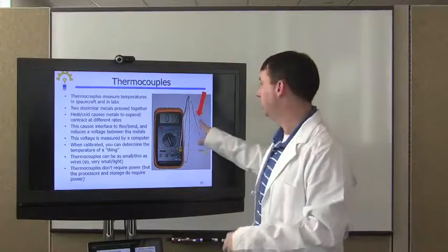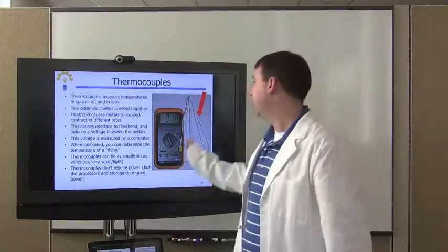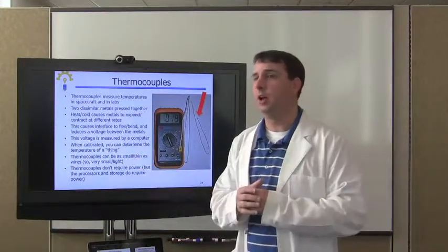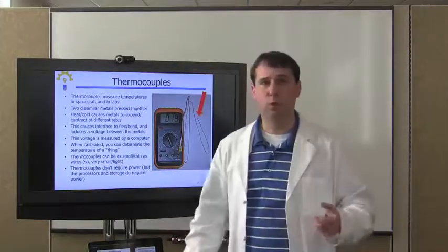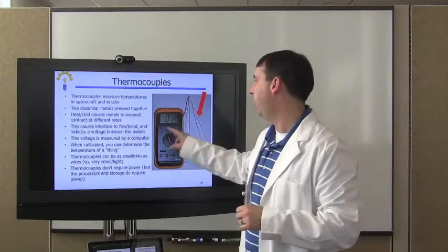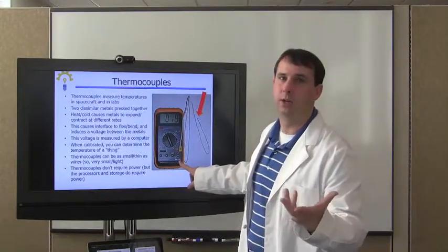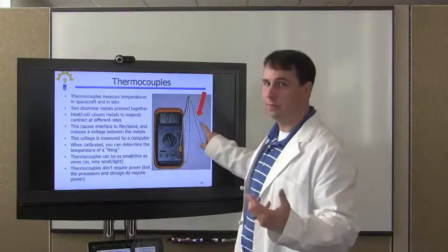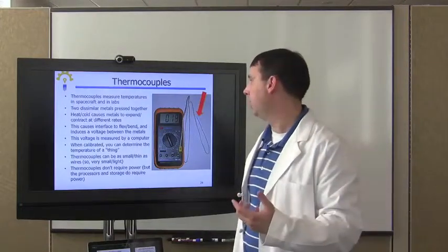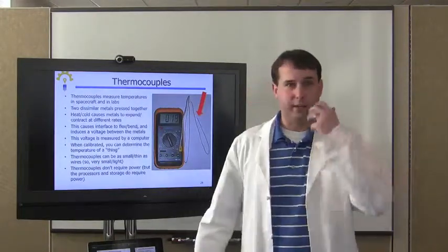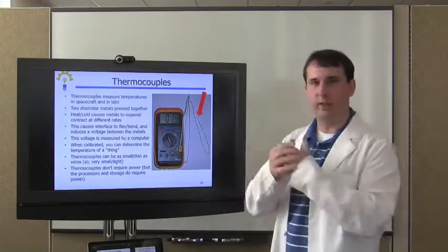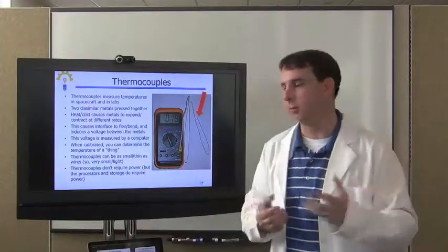Very low mass. It is literally just a wire. They can be long and metal if you want them to be, but they can be as small as a wire. They don't require power to work. They actually create a little bit of their own power, but you do require power to run your computer or whatever you're using to monitor the temperature. So the thermocouple itself doesn't require power, but the thing that monitors it does. That's a thermocouple. They're great, and they're so small you can weave them into things and embed them in things.